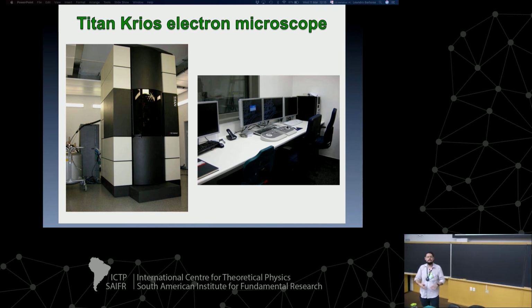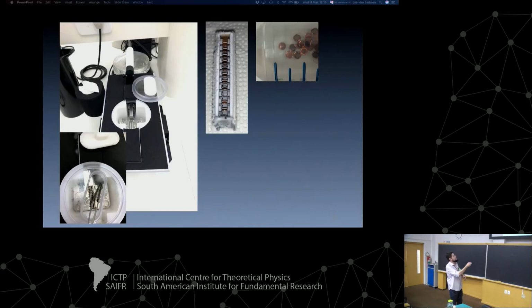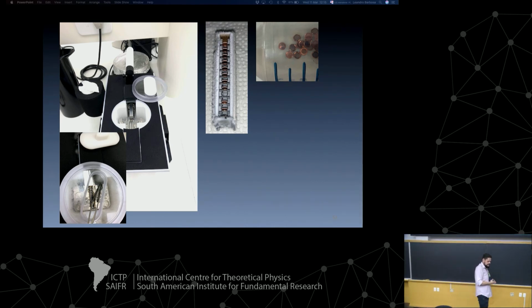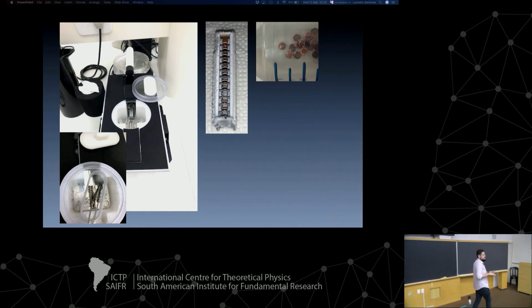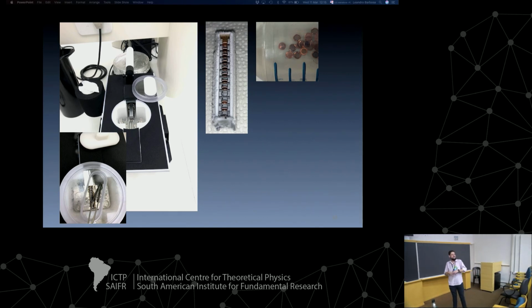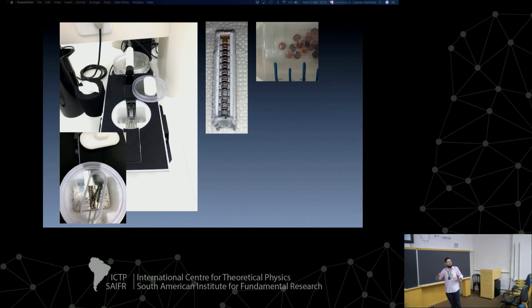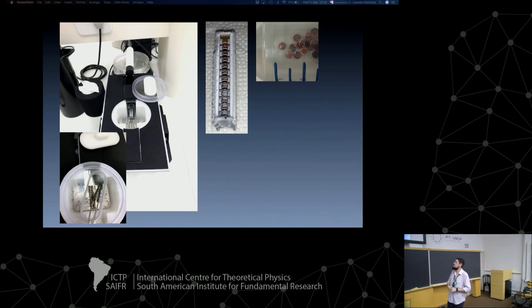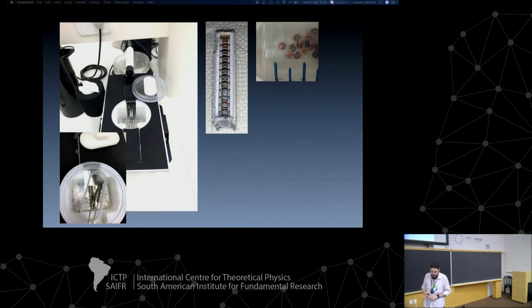They have several possibilities. For instance, with this equipment you can load, you see, several grids over here. You can load up to 11 grids. This means that you can do 11 different studies at the same time. Those are very, very automatic systems. So you can program the microscope to work for, let's say, 1, 2, or 3 weeks straight. It's working, it changes the grids itself. Of course, you must check once in a while because perhaps you have some problems during this procedure. But it's possible to work with this cassette with 11 grids to be measured at the same time.